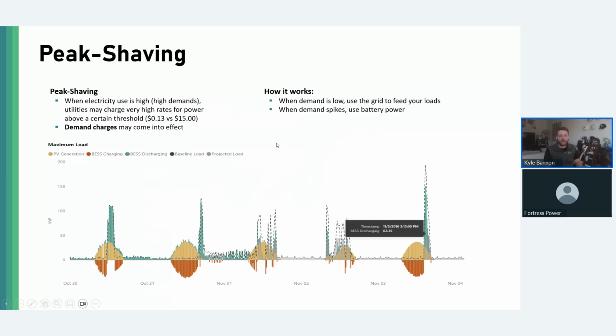The next strategy, probably the most lucrative and most common I see, is peak shaving. If you have short-duration spikes in your load profile — 15 minutes to an hour — that's perfect for a battery to step in and cap what the utility ever pulls above your projected baseline. In this graph, green is battery discharging, yellow is PV generation. The load spikes, but since there's PV, it offsets the load plus the battery, so we're barely pulling from the utility at all.